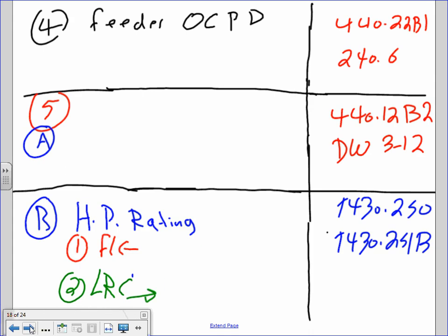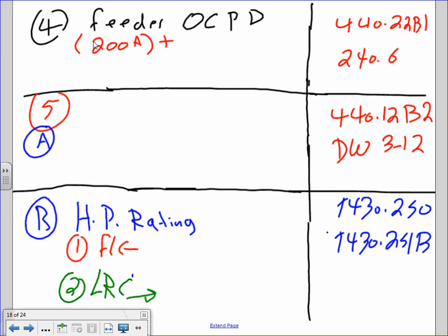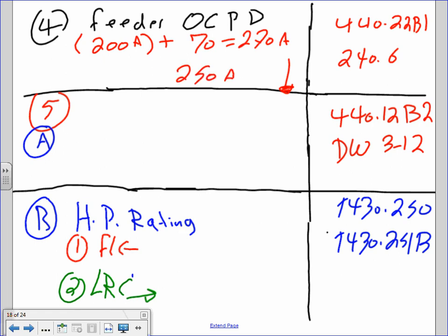Feeder overcurrent protection device, per 440.22B1 and 240.6: take the largest fuse of the system plus the full load amp of the other motor. The largest fuse is 200A plus full load amp 70A = 270 amps. Since 270 is not standard, go down to a 250-amp fuse for the feeder.